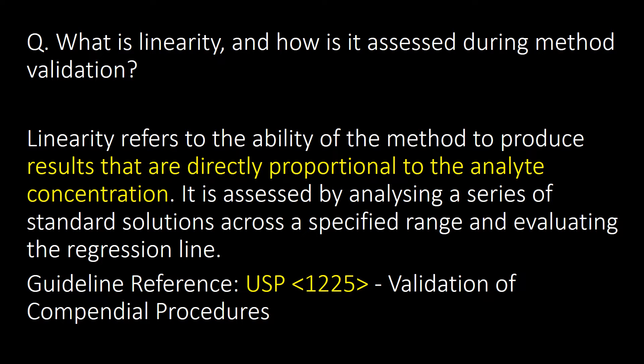What is linearity and how is it assessed during method validation? Linearity refers to the ability of the method to produce results that are directly proportional to the analyte concentration. It is assessed by analyzing a series of standard solutions across a specified range and evaluating the regression line. Guideline reference: USP Chapter 1225.